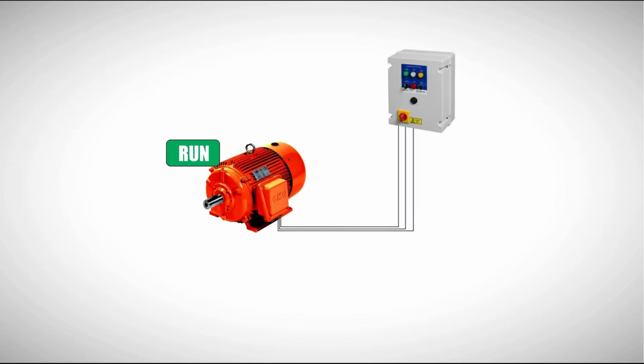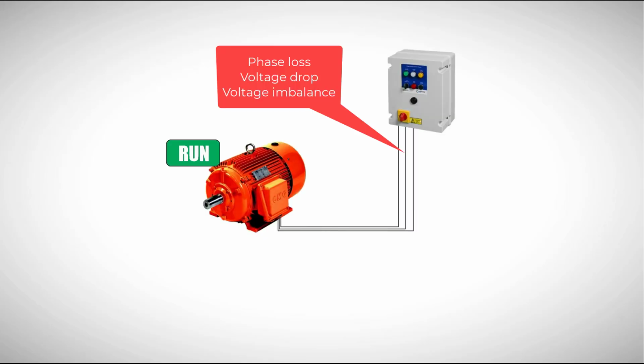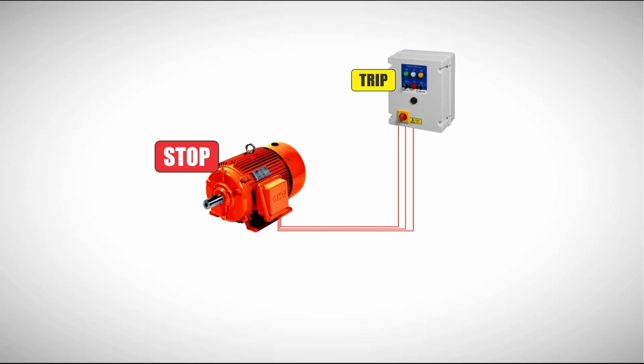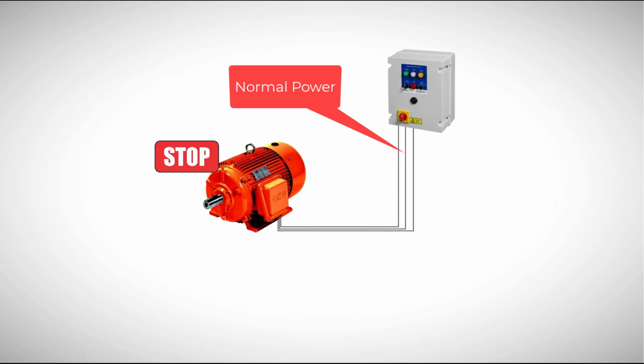When a fault occurs like a voltage drop, phase loss, or imbalance, the relay will immediately trip and disconnect the load to protect the equipment. Now, once the fault is cleared and the power supply returns to normal, the relay does not instantly reconnect. Instead, it starts counting the delay time you've set.